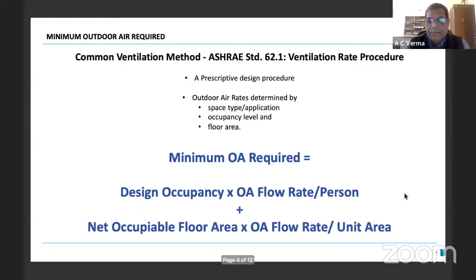This is two-part, because one is the requirement of fresh air for breathing purposes, and that is the essential portion. So that is based on per person. And then there is contaminant generation in the occupied area from the building interiors. So that component of the minimum outdoor air is based on your unit floor area. So as we see, this is the minimum air required.